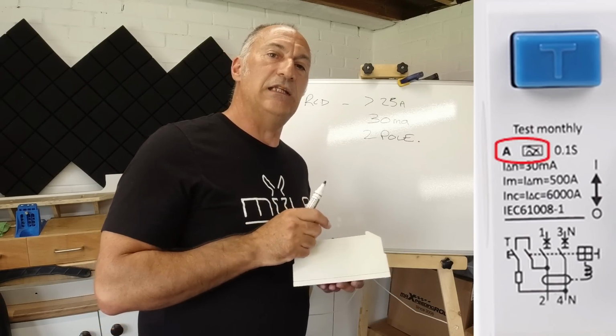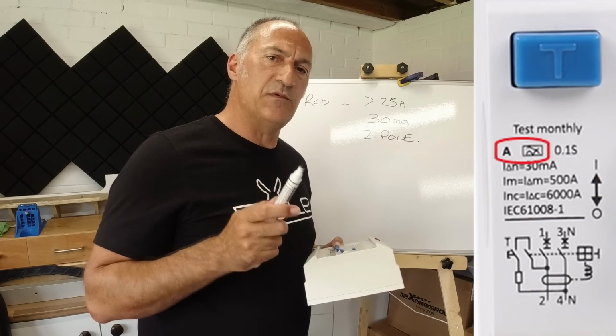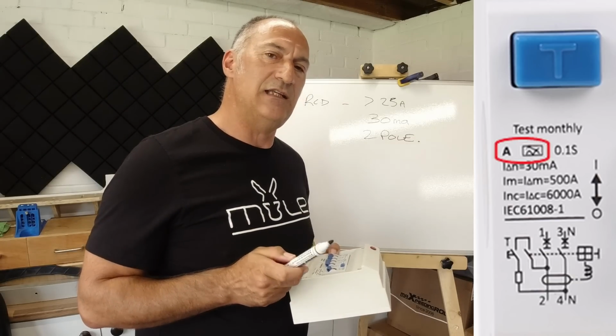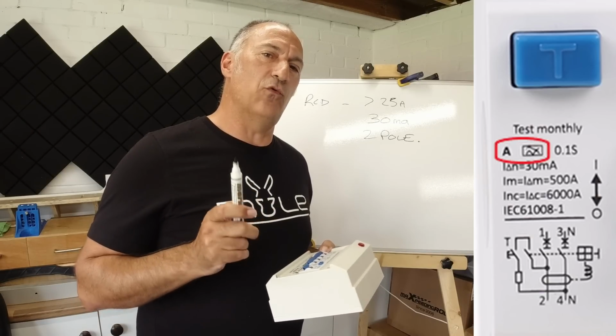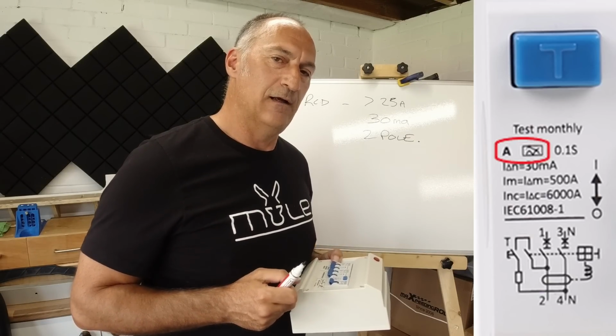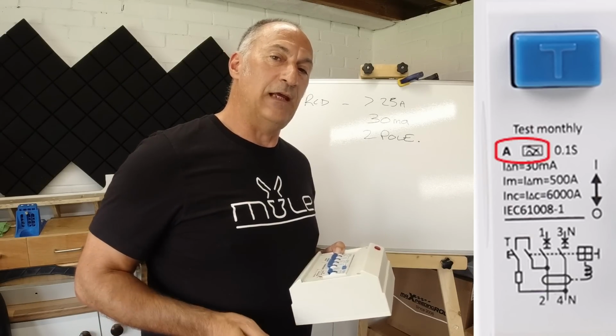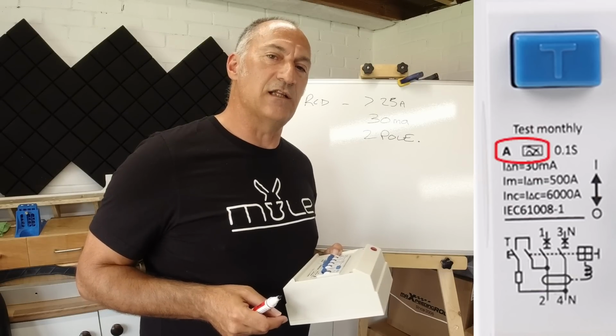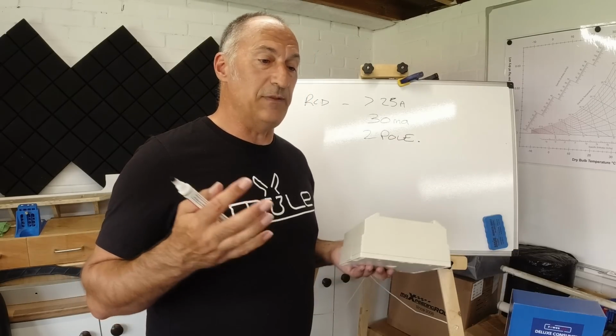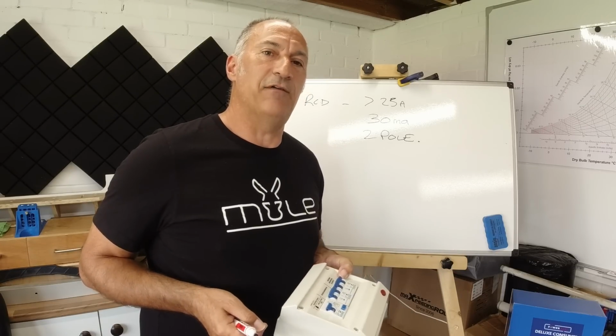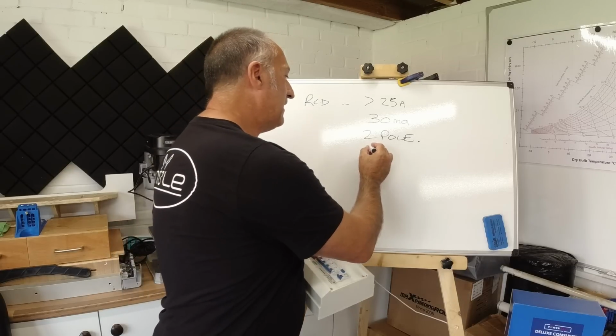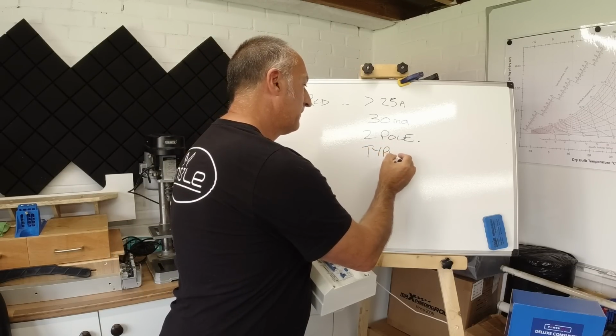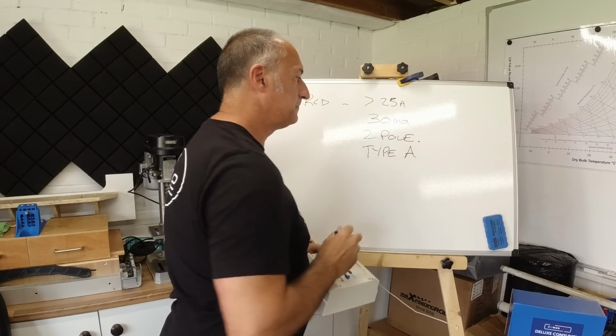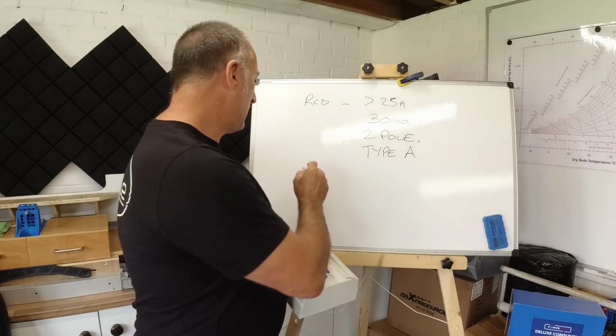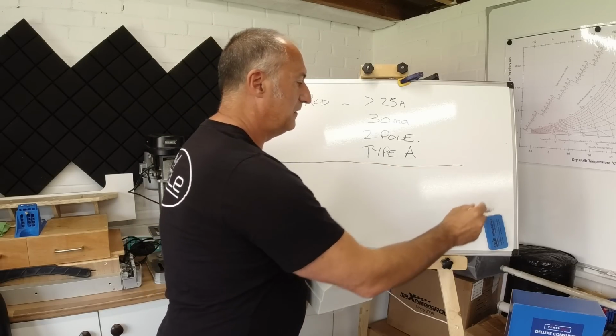So modern RCDs that you need to be looking for, as a minimum standard, would be a type A RCD, which allows for a small amount of DC leakage current and will still break even if those devices are connected to the circuit. As we're going to be using modern electronic devices in our camper van, we need to have a type A RCD as a minimum. So those are the requirements for our RCD.